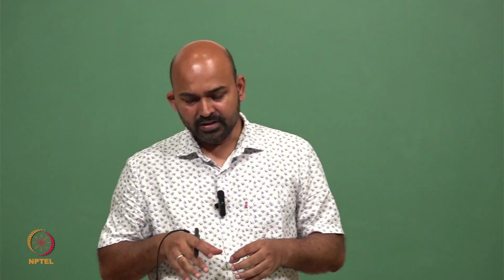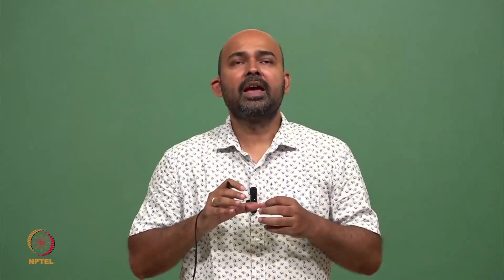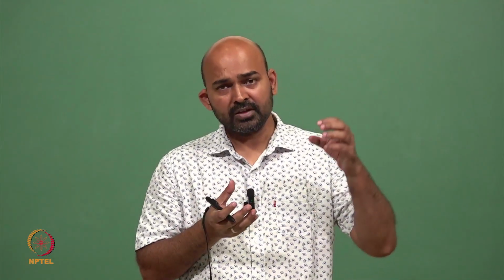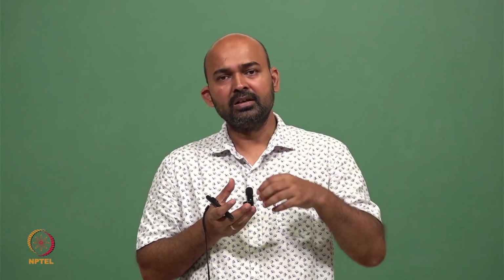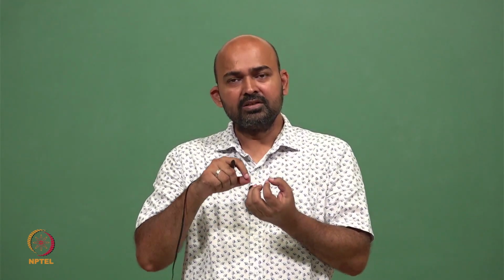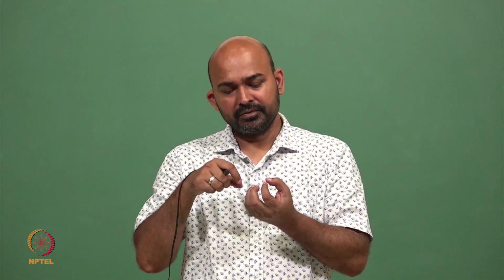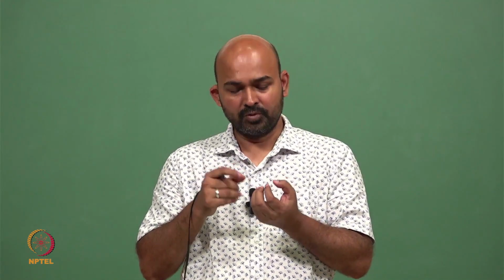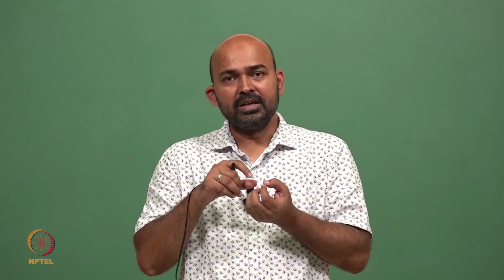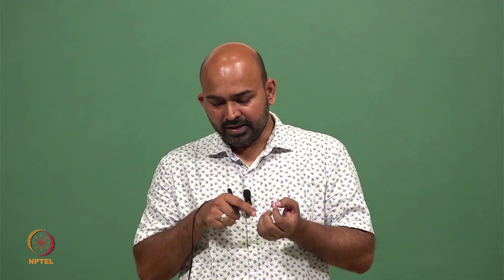The third is the detector material should be transparent to the wavelength of its own emission. So we have a material, when we shine the radiation on it, after accepting this radiation, this material is going to generate the visible photon, the optical photon, and this material should be transparent for this particular wavelength of photon.